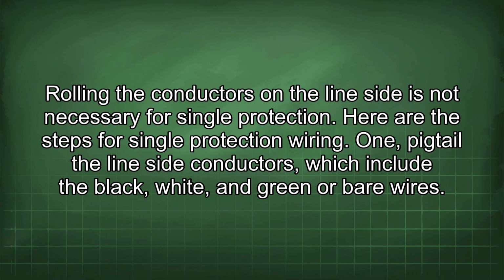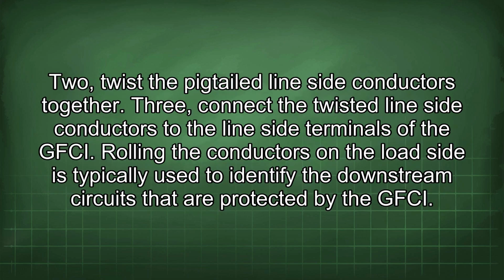Here are the steps for single protection wiring. 1. Pigtail the line side conductors, which include the black, white, and green or bare wires. 2. Twist the pigtailed line side conductors together. 3. Connect the twisted line side conductors to the line side terminals of the GFCI.